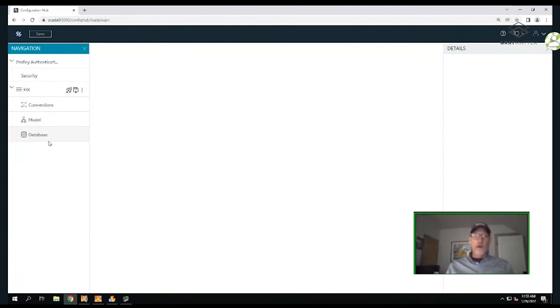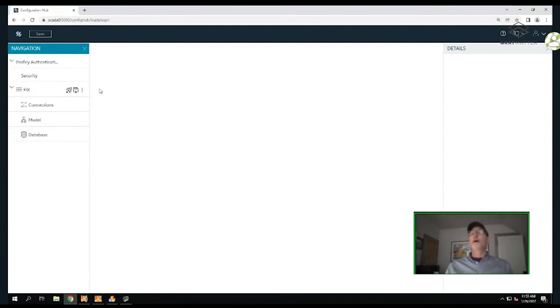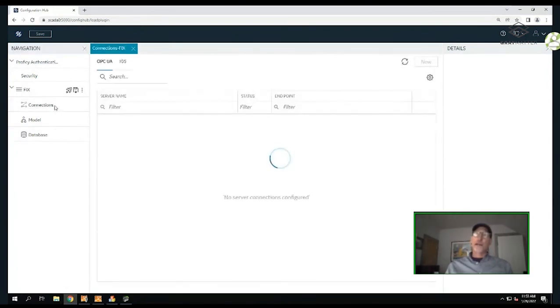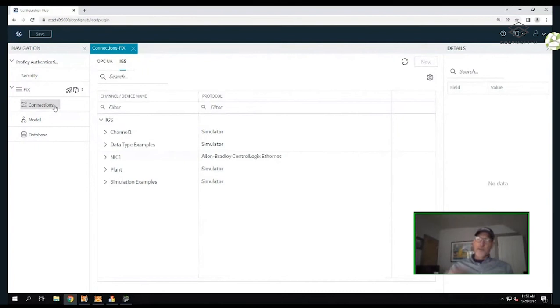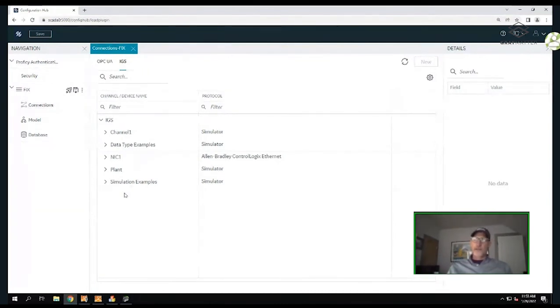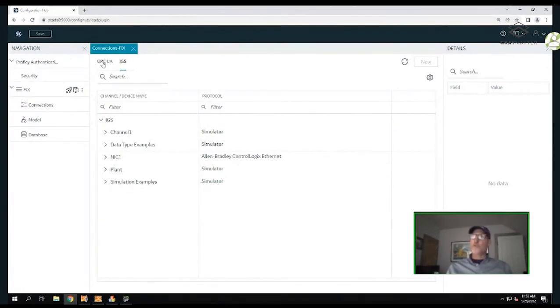I'll start off with simple tag configuration. If I have a couple of new points in my controller that I'd like to use in the iFIX environment, I would hit Connections - this interrogates the IGS configuration and gives me a list of everything in the Industrial Gateway Server. This will also work with OPC UA, so if you have an OPC UA device, it works the same way.